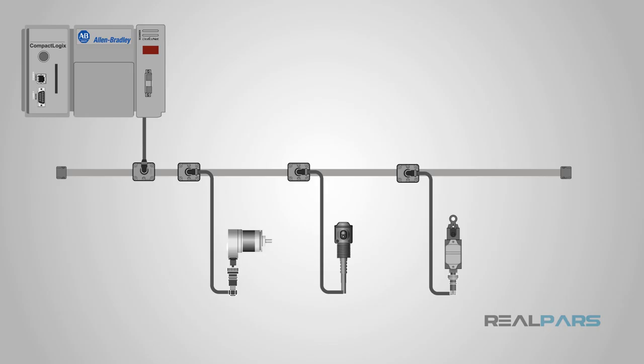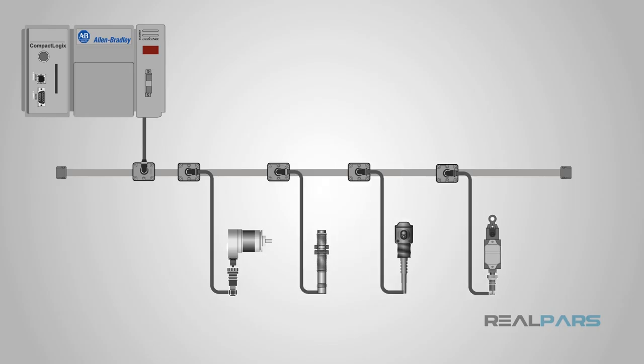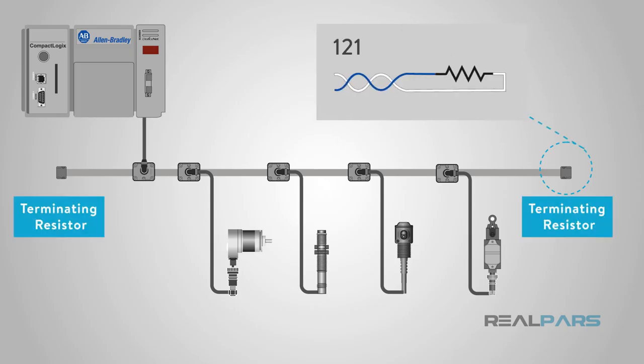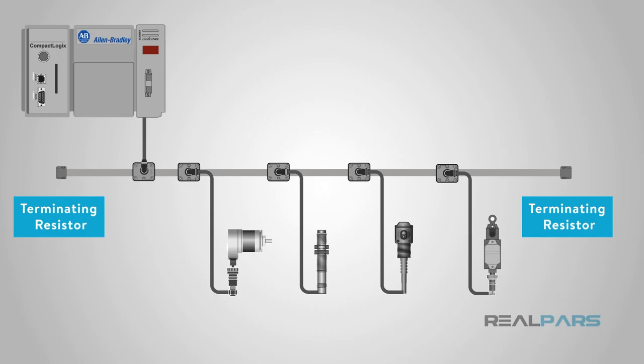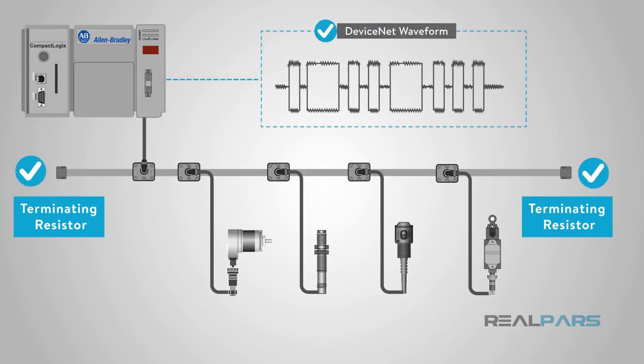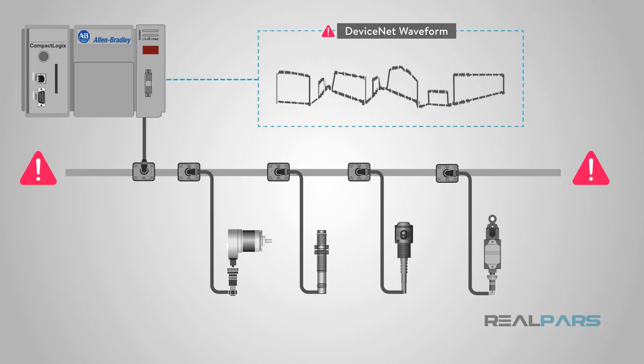Since there are no predetermined cord lengths, you can put connections to the flat cable anywhere on the line, making it great for device placement. The trunk line requires a 121-ohm, 1%, 0.25-watt or larger terminating resistor at each end of the trunk, connected directly across the signal wires — blue and white. The terminating resistors reduce electrical noise, and without them in their correct place, the DeviceNet will not work properly.